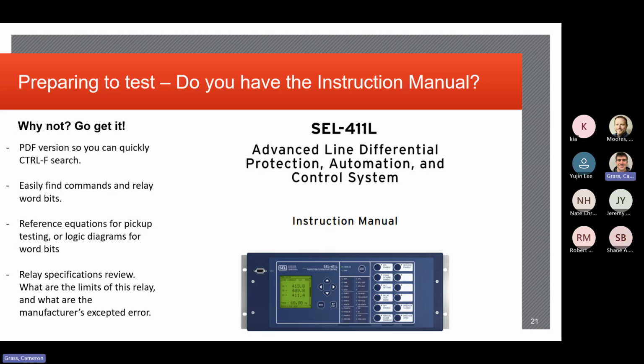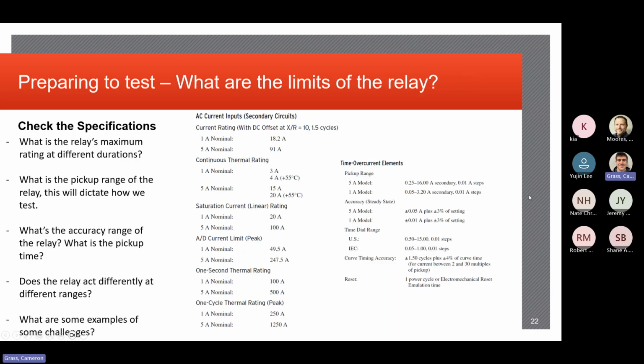Yep, for sure. The instruction manual is going to be your best friend and your worst nightmare when you're out in the field, because it's going to have every answer you need, but it's going to be the worst way to ever find the answers. Nice thing about nowadays, you can Control F in a PDF on your laptop to navigate the manual a lot easier, to find certain commands or certain elements that you need to learn about a little bit more, or figure out how you're going to pick up or how you're going to test. But realistically, this is going to be your best source of information to determine the equations you need to pick up elements, do your testing, test your logic diagrams based on the design intent, and review the specs as well. So it's a blessing and a curse, that's for sure.